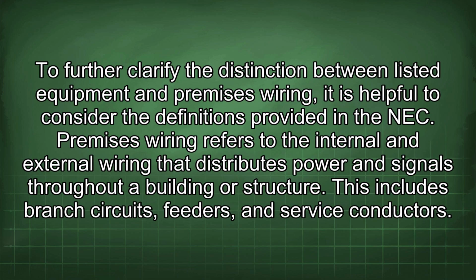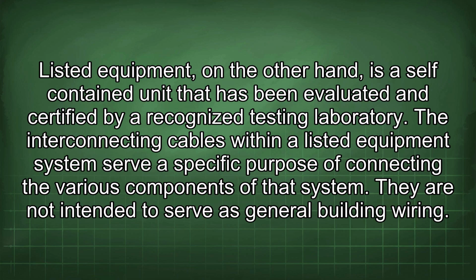To further clarify the distinction between listed equipment and premises wiring, it is helpful to consider the definitions provided in the NEC. Premises wiring refers to the internal and external wiring that distributes power and signals throughout a building or structure. This includes branch circuits, feeders, and service conductors. Listed equipment, on the other hand, is a self-contained unit that has been evaluated and certified by a recognized testing laboratory. The interconnecting cables within a listed equipment system serve a specific purpose of connecting the various components of that system. They are not intended to serve as general building wiring.